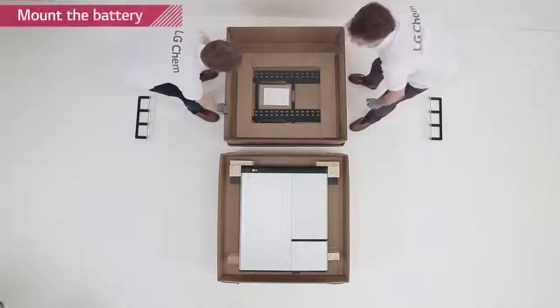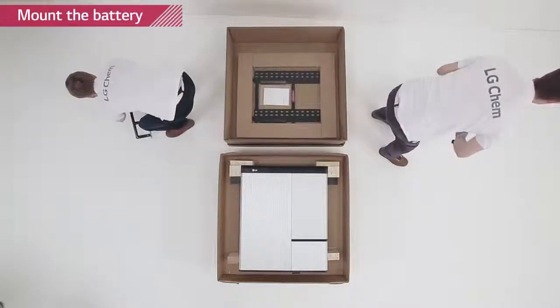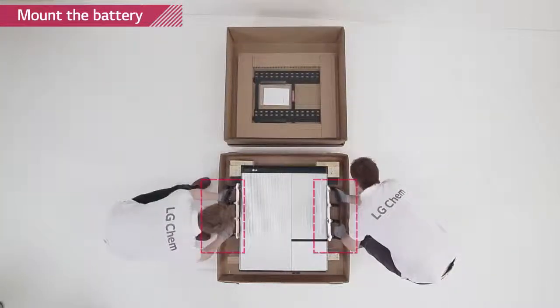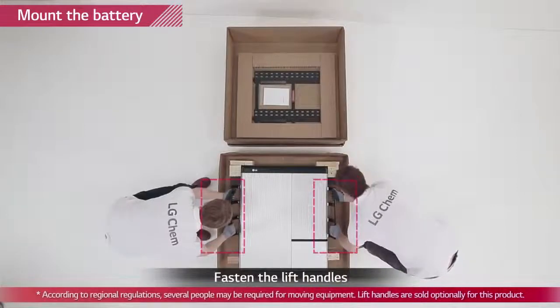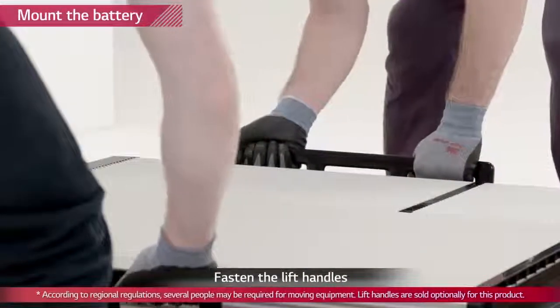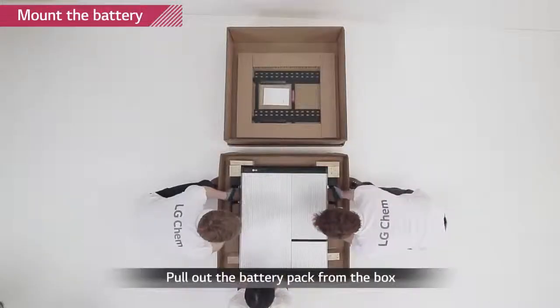Attach the lifting handles to the hex socket screws located at the back of both sides of the RESU pack. Lift the battery pack using the handles. Handle the RESU 10H carefully as it weighs about 100 kilograms. Note that the wall on which the battery pack will be mounted must have the capability to support weight over 150 kilograms.